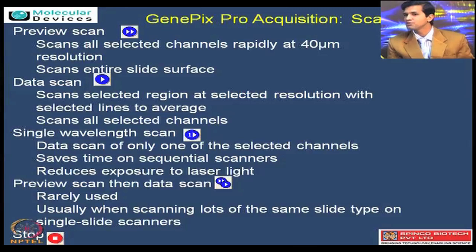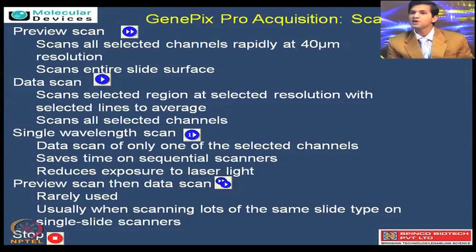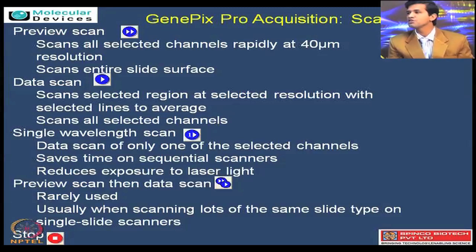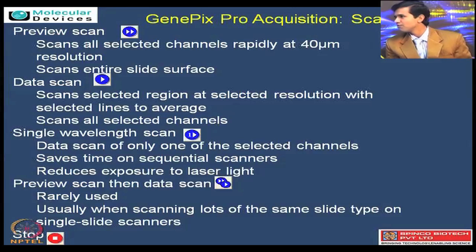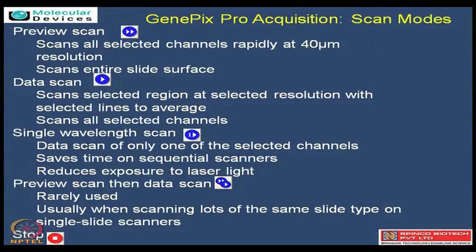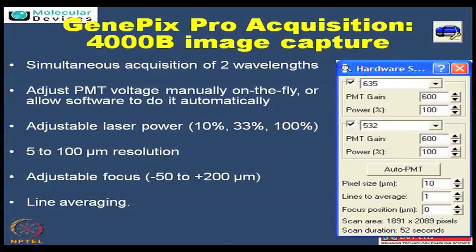For example, when you start with the preview scan, you decide on which best pixelation suits you and which laser power suits you. Once those decisions are made you can go for your data scan. People prefer this approach because there is sometimes a bleaching effect on the fluorophores, so they want to avoid longer exposure. Multiple scanning is avoided for this reason. If your application requires only one wavelength to be scanned, you can select only a single wavelength scan in the tab.